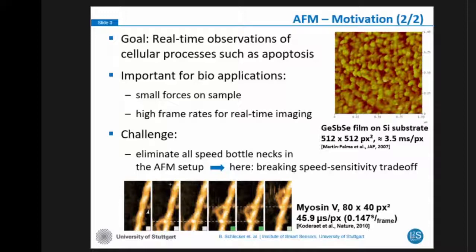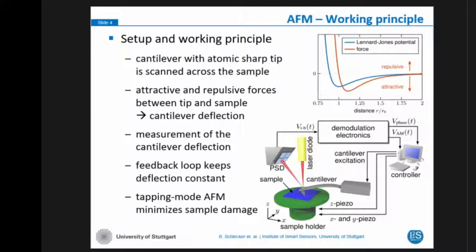Here on the lower part of the slide you see the basic principle of an AFM system. It consists of a cantilever with a sharp tip attached at its end, and this cantilever is scanning across the sample in a raster fashion. Due to the attractive and repulsive forces between the tip and the sample, the cantilever is being deflected. We then measure the deflection, most commonly with the so-called beam deflection method, and demodulate this deflection signal in our demodulation electronics.